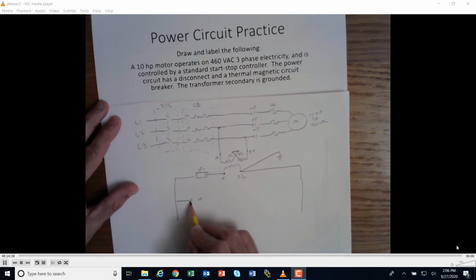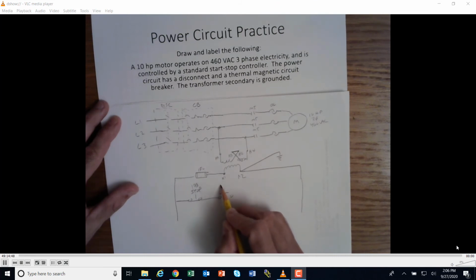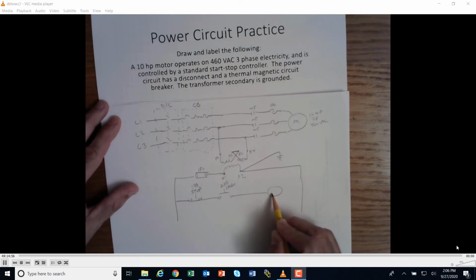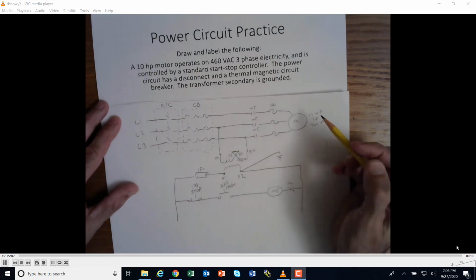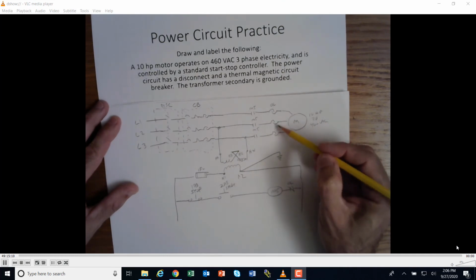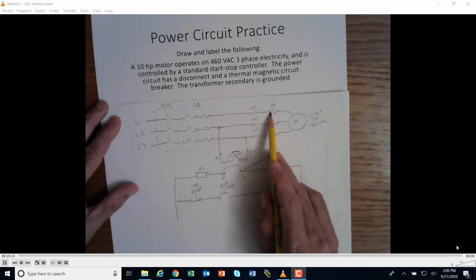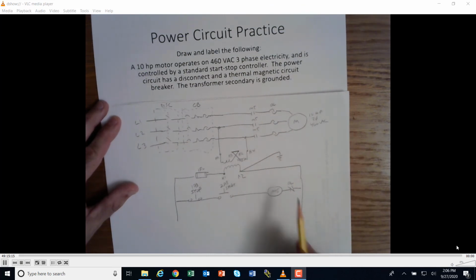So we're going to start here with 1 PB. We'll call that stop. And to go to a normally open 2 PB. That can be start. And then we're going to go to a motor starter. And then we're going to put the normally closed contacts from the overload up here. Okay. So remember, this overload is built into the motor starter. We're going to be talking a lot about this. And if these get hot, this opens.